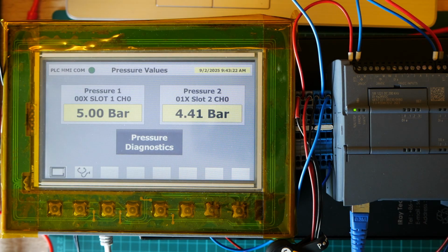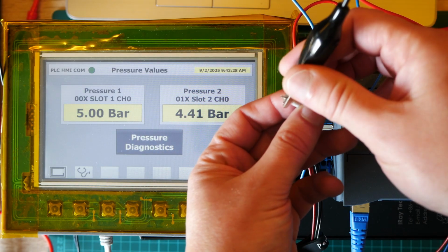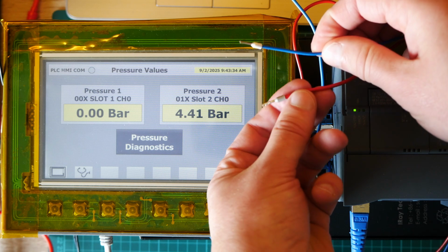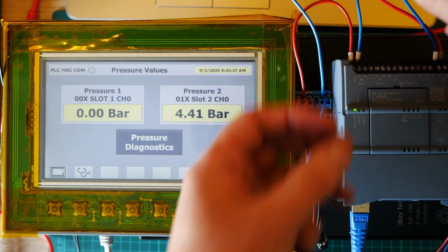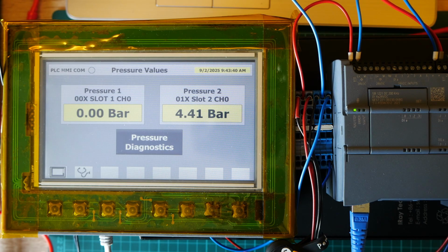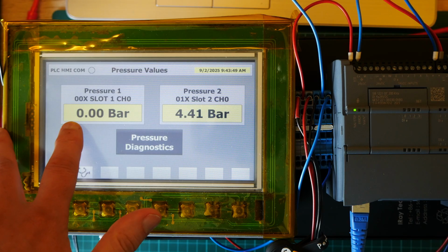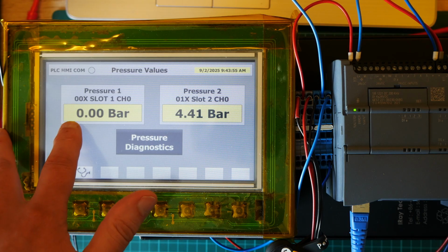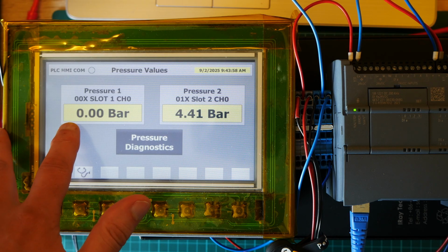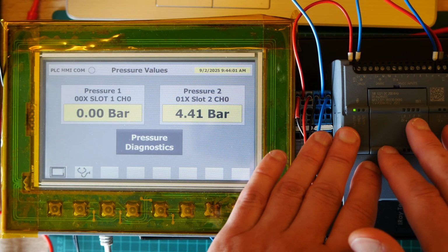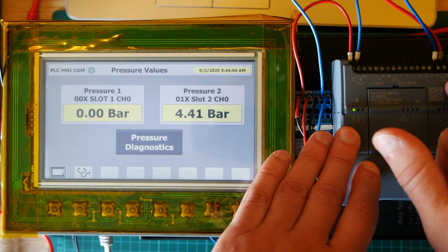First thing to do, I think the best way is to just disconnect completely the power to the analog input. So right now the wires are disconnected completely. Obviously the device should be stopped, maybe in emergency mode, so the process should not run. So what he should see is 0 bars. If he sees anything else, then it means the problem is on the PLC side or in the analog input side.